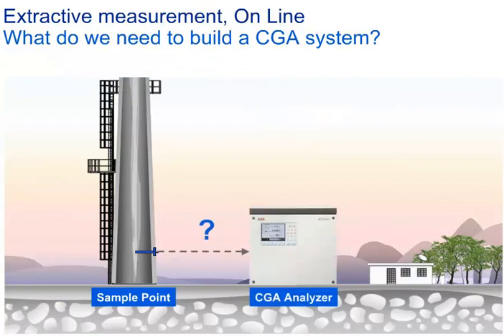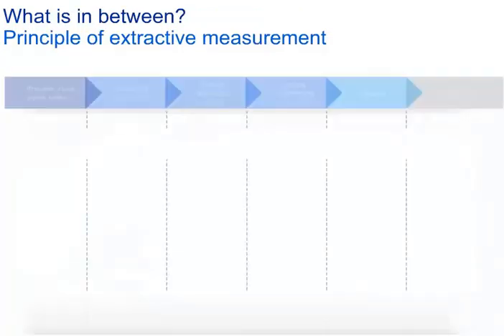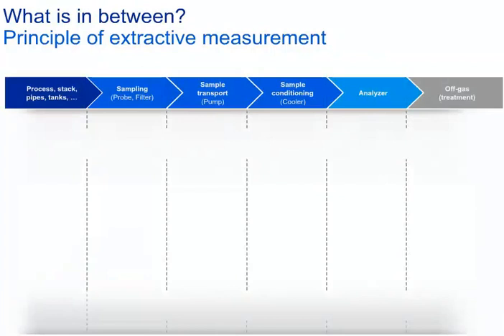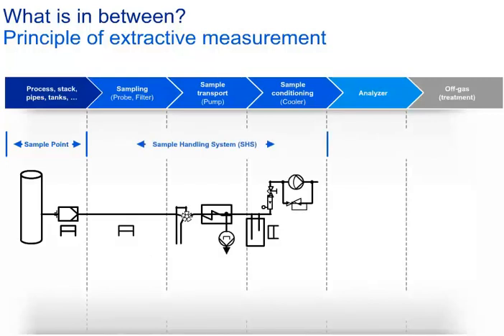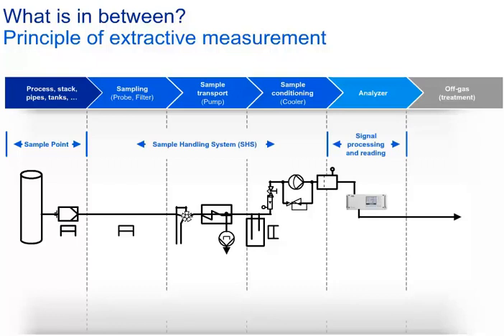In the next section we will focus on the extractive measurement and the system components typical for the design of a complete continuous gas analysis system. After drawing the gas from a stack or a process pipe, the sample gas will be filtered from dust load and transported in a sample line — often heated to prevent condensation from wet gases. The gas enters the sample handling system, which prepares the sample gas for accurate and reliable measurement without damaging the gas analyzer. Finally, the conditioned gas will be measured inside the analyzer and released into the atmosphere or back into the process.